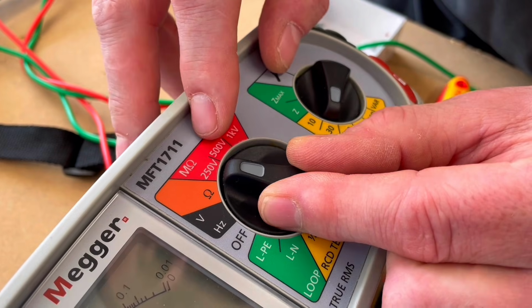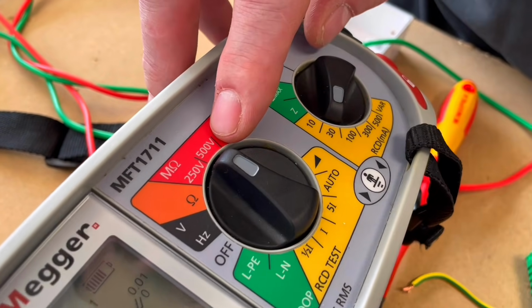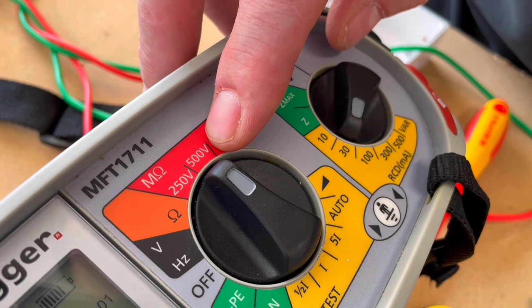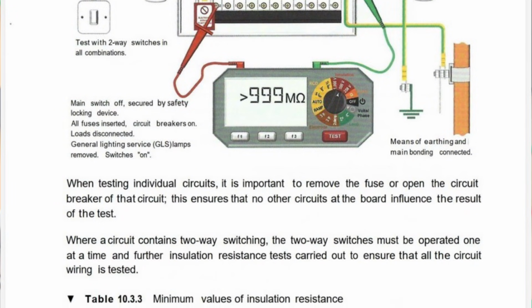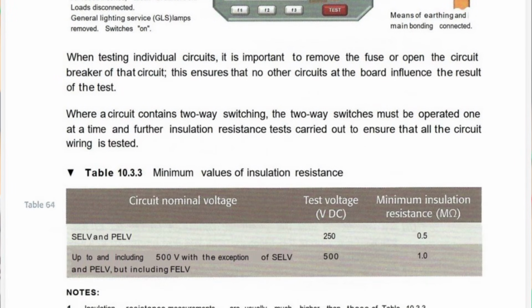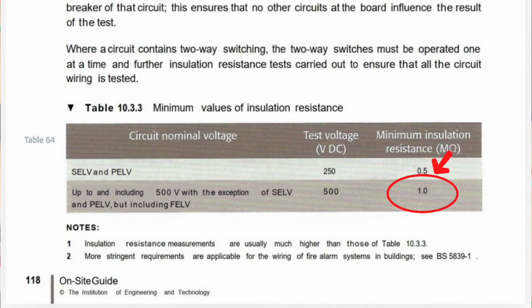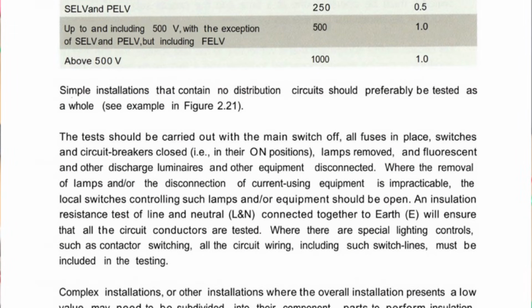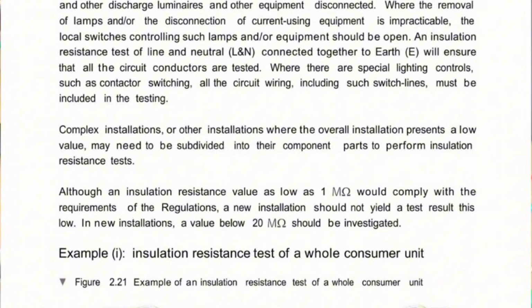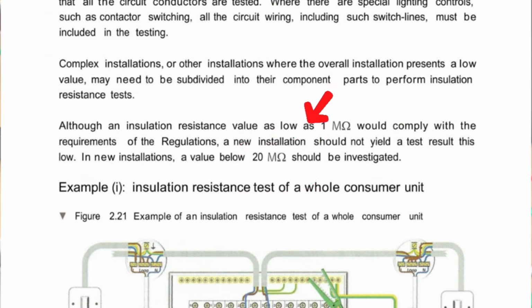And now there's 3 voltages to choose from. For our system, we're going to test it at 500 volts DC. And the on-site guide says that we should achieve a minimum insulation resistance of 1 megohm. However, further investigation at 2 megohm. But if you look in the guidance notes 3, it says for a brand new installation, it shouldn't be less than 20 megohm. Okay, so we've got a brand new installation.